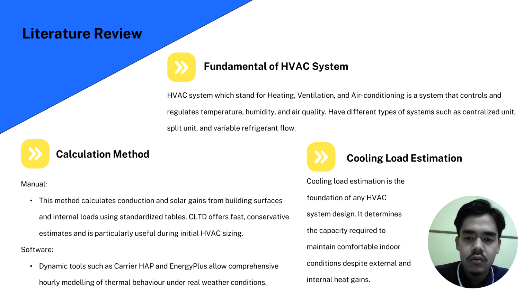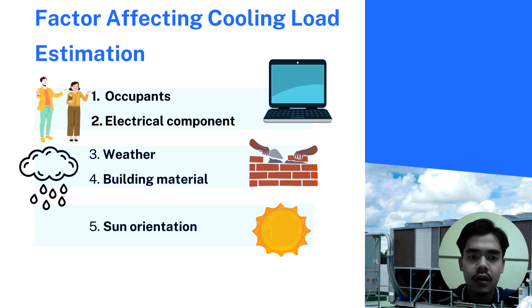And lastly, the cooling load estimation. Cooling load estimation is the foundation of any HVAC system design. It determines the capacity required to maintain comfortable indoor conditions despite external and internal heat gains. There are a lot of factors that affect the cooling load estimation. Firstly, occupants and electrical components. Internal heat gains from occupants and equipment are major factors in a small room. This is due to occupants and electrical components that produce major latent heat.